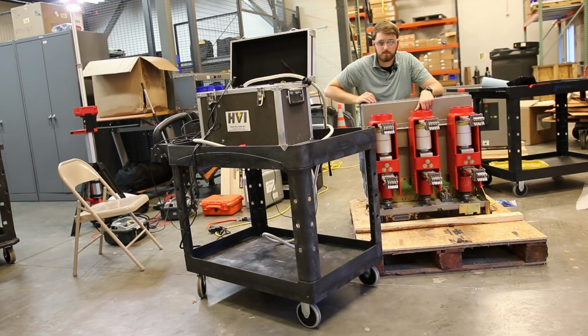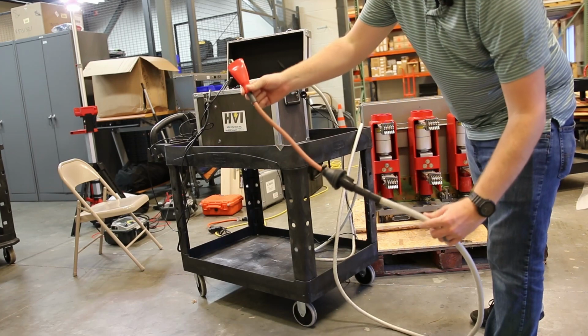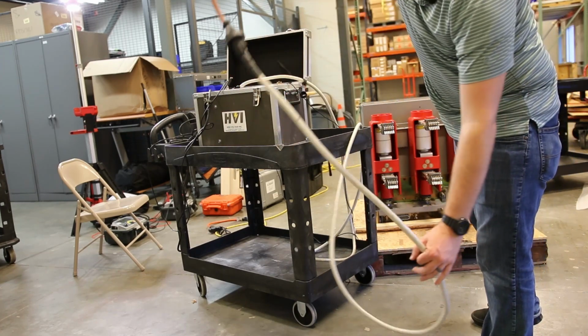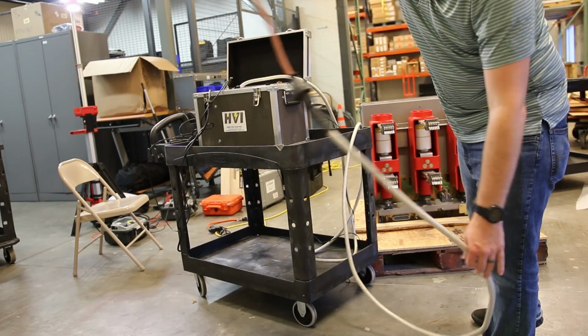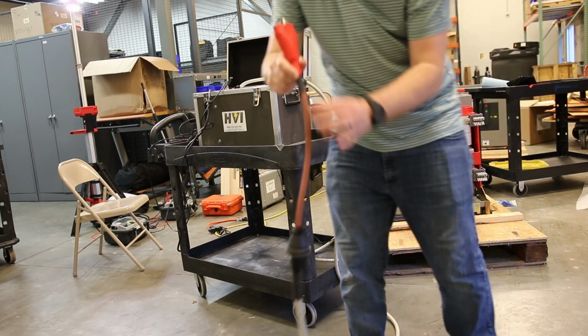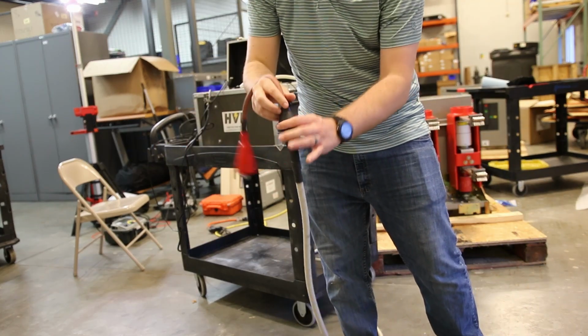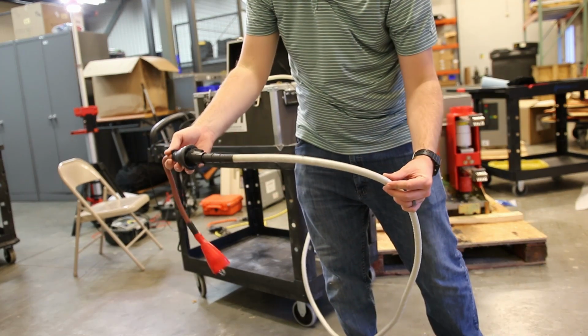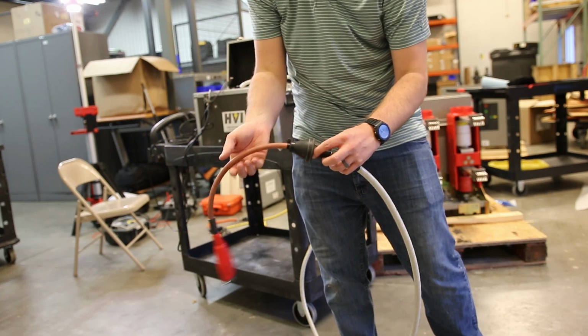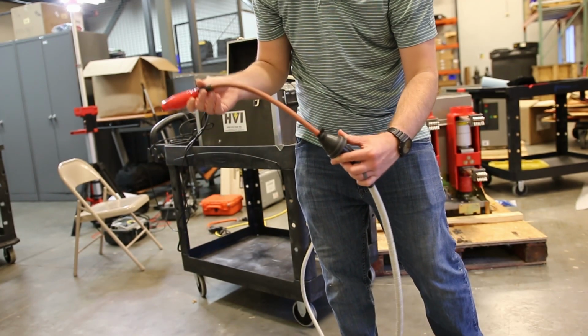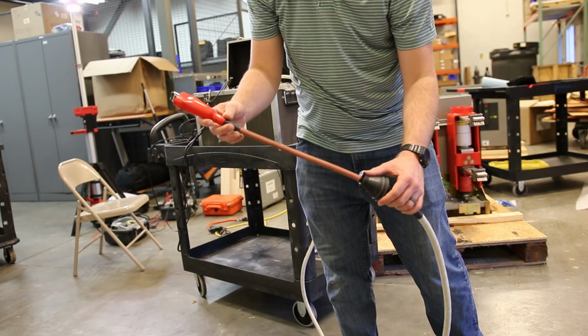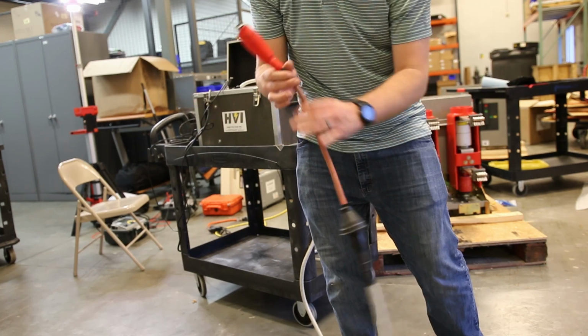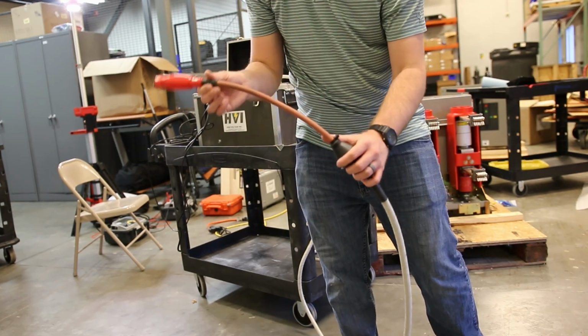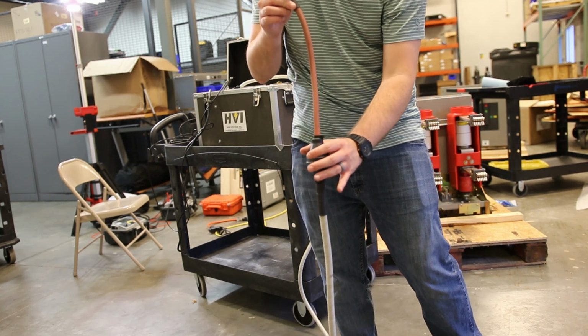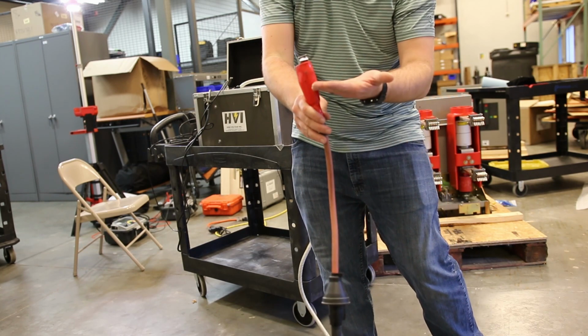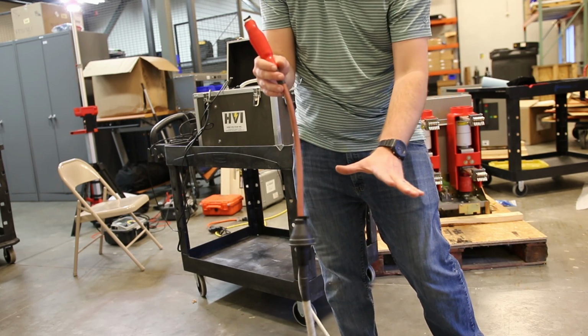on the test set. On most hipot leads, you'll see most of it is this white, or sometimes they're black, sometimes they're another color. And then you've got this part right here. So the white part is shielded. You've got this little gland here, it's sort of like a weather head. And then the red lead is unshielded. So this is just insulated. So we really wanna try and keep everything between here and the tip, just consider that whole thing hot.